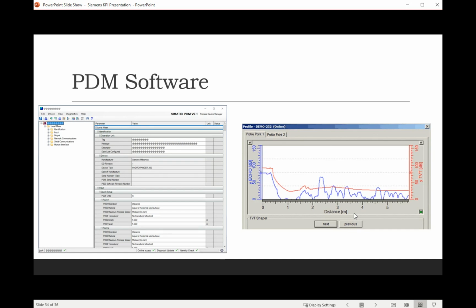So let's say you have an older style Hydroranger and it fails and you want to replace it with a new HMI version. You install it, hook up to it with PDM software, and then you find the file from the Hydroranger that failed, hit upload, and you can have all those parameters downloaded into that new Hydroranger. So you don't need to do any programming. You just hit the download button, and then you're back up and running. Pretty simple, easy way to do it, and easy to just keep all your Hydrorangers in one place.